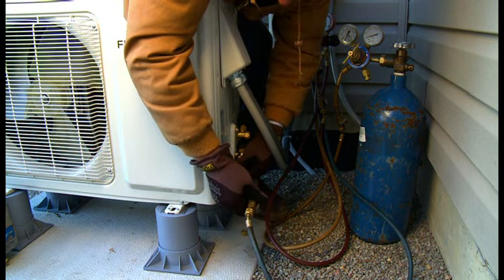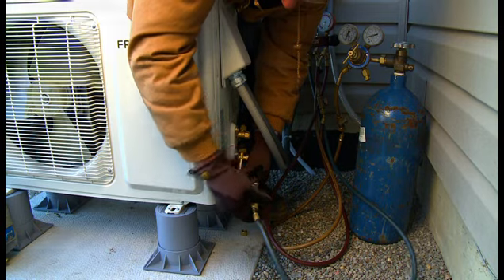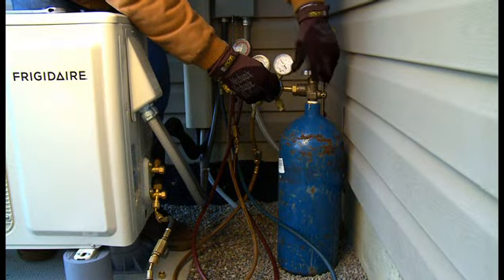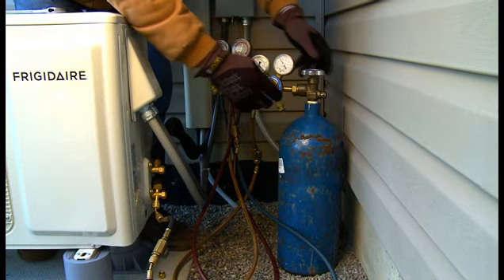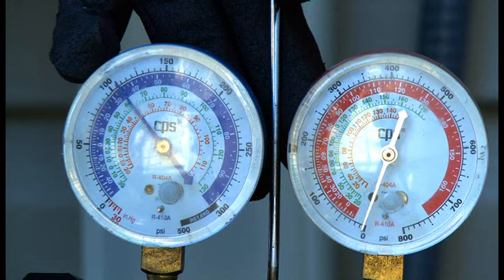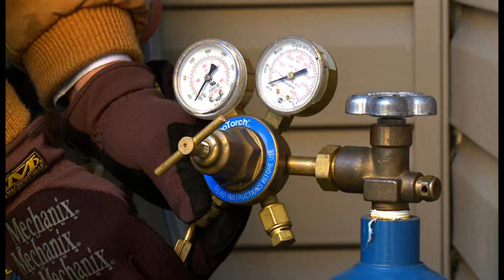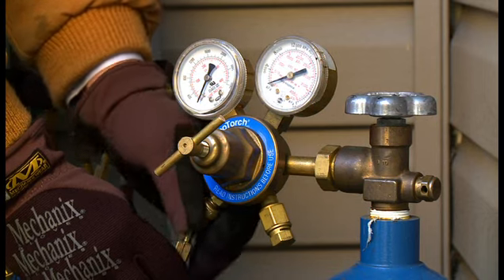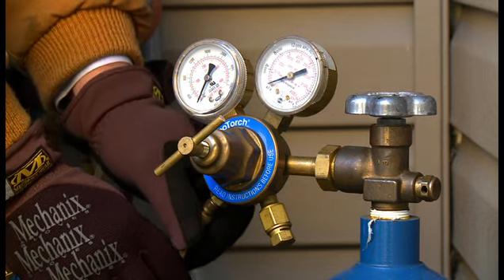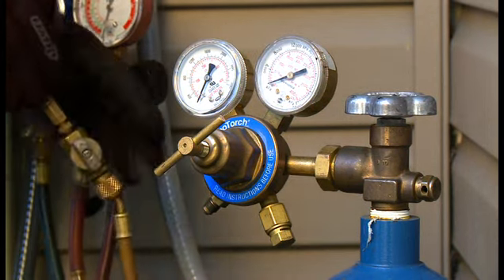Install the adapter to the access port's 1/4 inch connection. At the adapter, install the nitrogen tank's pressure control valve. Test the connections under pressure of at least 100 psi for about 15 minutes. If the pressure holds, the lines are free of leaks. Close the nitrogen tank. Release the nitrogen from the appliance. Remove the pressure hose from the nitrogen tank.